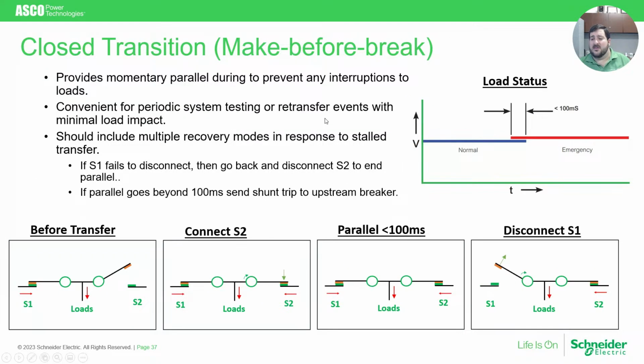The last mode that I'll cover today is the closed transition mode. Closed transition switching is actually a make before break operation, and actually does the opposite of what you usually see a transfer switch do. Usually the job of a transfer switch is to ensure that you are never paralleling two different sources of power. Well, a closed transition transfer switch monitors several parameters within it, and when those parameters all align and the sources are passively synchronized, it goes ahead and actually closes source 2 before opening source 1. So meaning there is a momentary parallel operation.